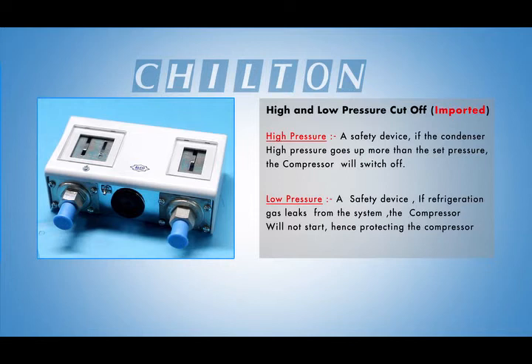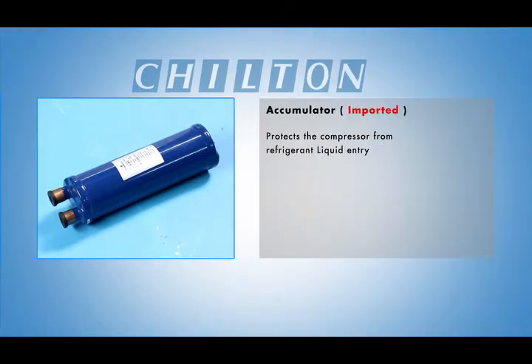High and low pressure cutoff. High pressure, a safety device: if the condenser high pressure goes up more than the set pressure, the compressor will switch off. Low pressure, a safety device: if refrigeration gas leaks from the system, the compressor will not start, hence protecting the compressor. Accumulator protects the compressor from refrigerant liquid entry.